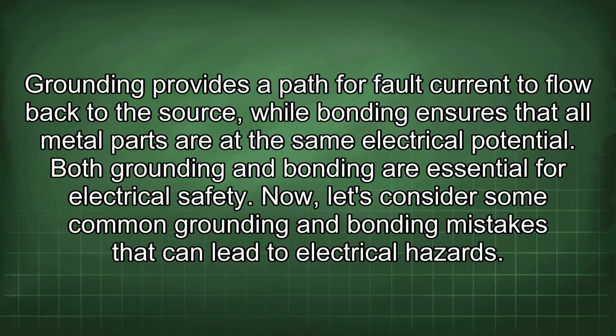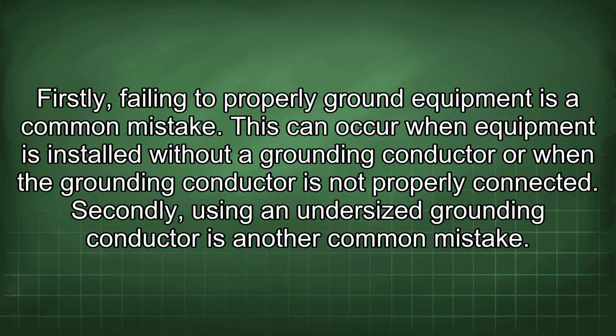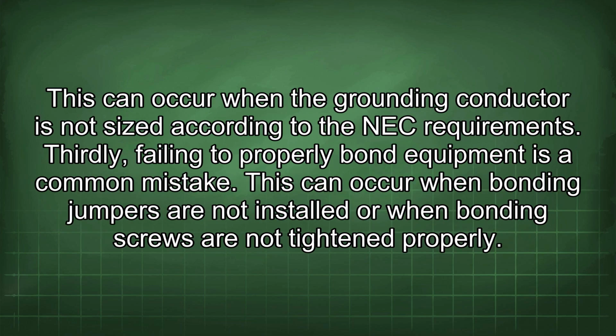Now, let's consider some common grounding and bonding mistakes that can lead to electrical hazards. Firstly, failing to properly ground equipment is a common mistake. This can occur where equipment is installed without a grounding conductor or when the grounding conductor is not properly connected. Secondly, using an undersized grounding conductor is another common mistake. This can occur when the grounding conductor is not sized according to the NEC requirements. Thirdly, failing to properly bond equipment is a common mistake.